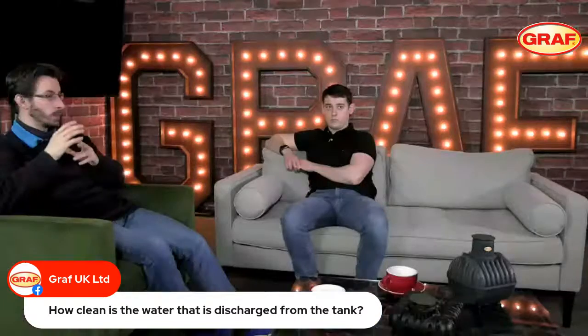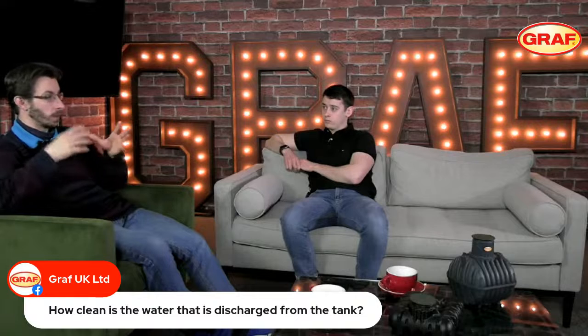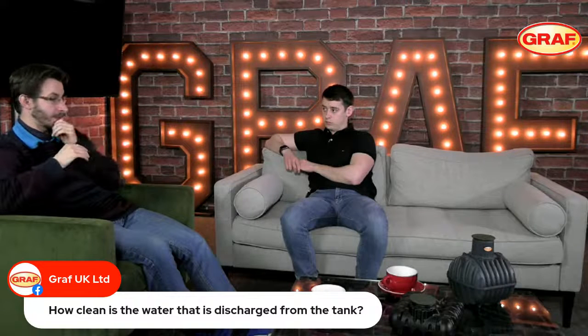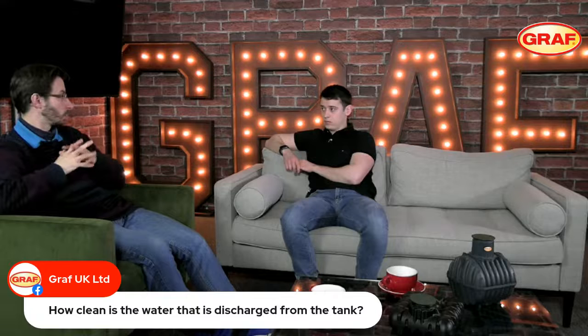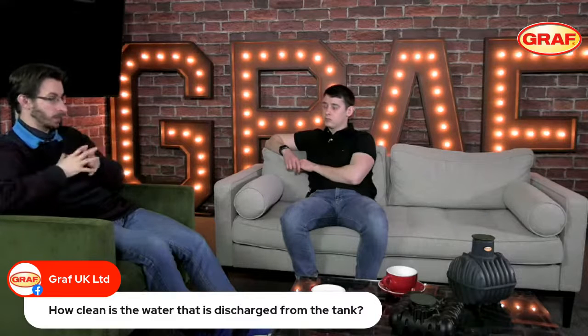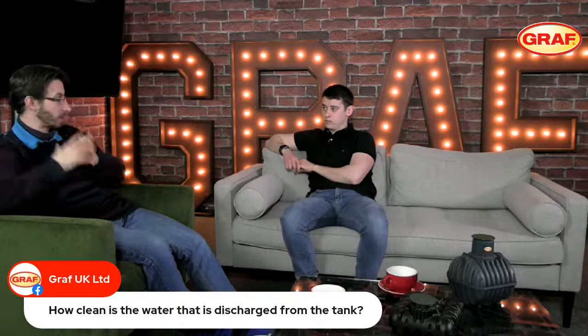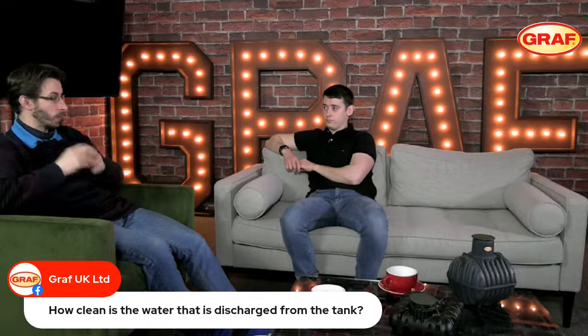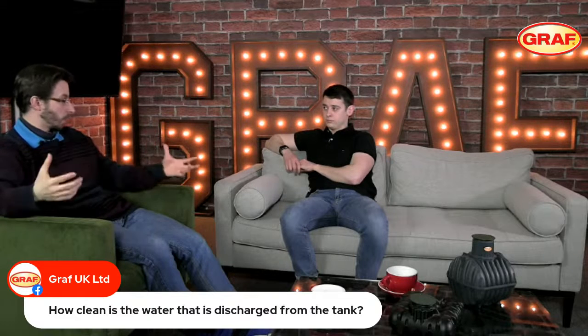The reason why we can't say the water is super good, of course, is because of the pathogens and microorganisms that escape in that water as well. We are looking at future technology to treat that water further through disinfection. This could be through UV or potentially chlorine dosing in a reaction tank afterwards. Again, that would get the water quality to potentially a standard where you could reuse it back in your garden, but there's no certification in place at this moment in time in the UK to say that you can do that. So the water itself is absolutely superb in terms of what comes into the tank.